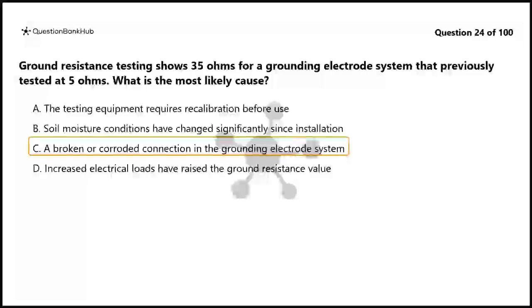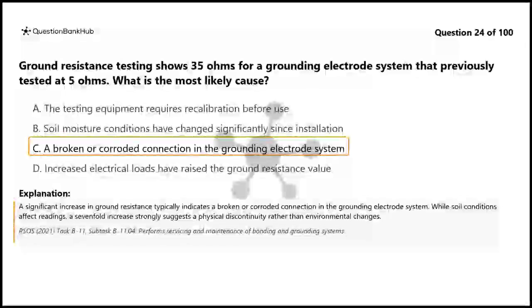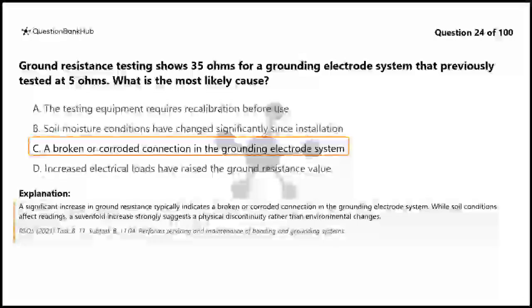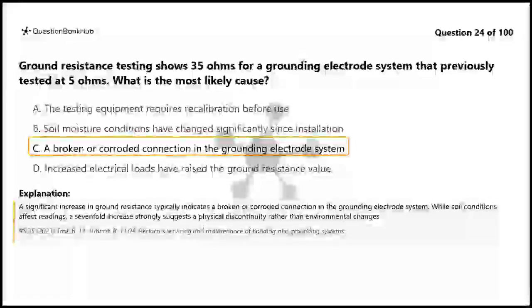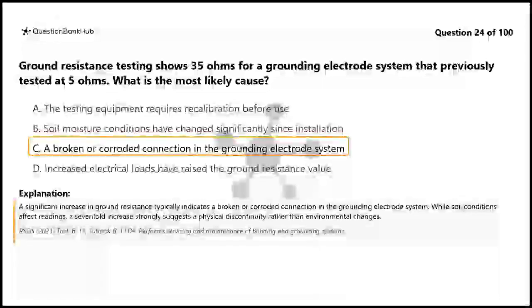The correct answer is C. A broken or corroded connection in the grounding electrode system. A significant increase in ground resistance typically indicates a broken or corroded connection in the grounding electrode system. While soil conditions affect readings, a 7-fold increase strongly suggests a physical discontinuity rather than environmental changes.